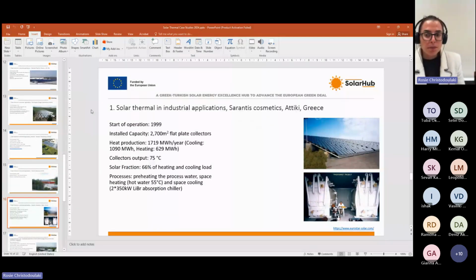One of the oldest and biggest solar thermal installations in industries is this of the Sarantis Cosmetics, which is based in Attica in Greece. This solar thermal system is also still running. It started its operation in 1999. The installed capacity is 2,700 square meters of flat plate collectors, and it can produce heat of 1,719 megawatt hours per year.